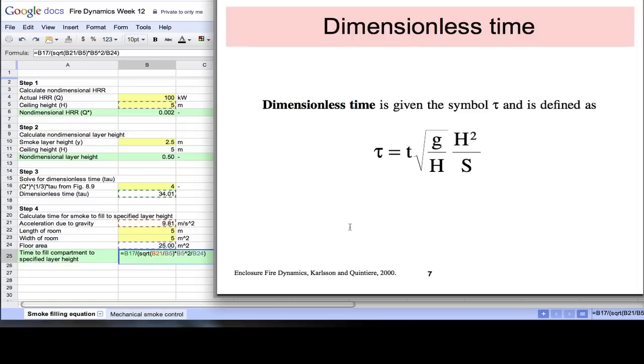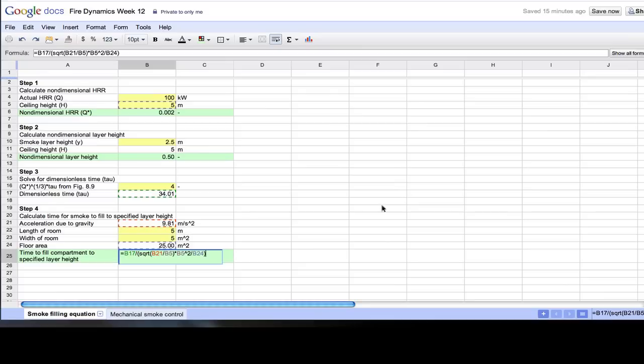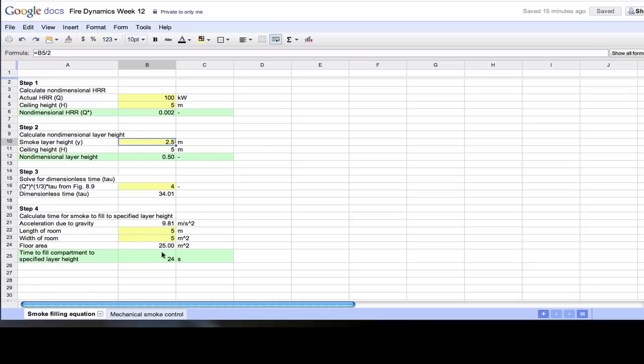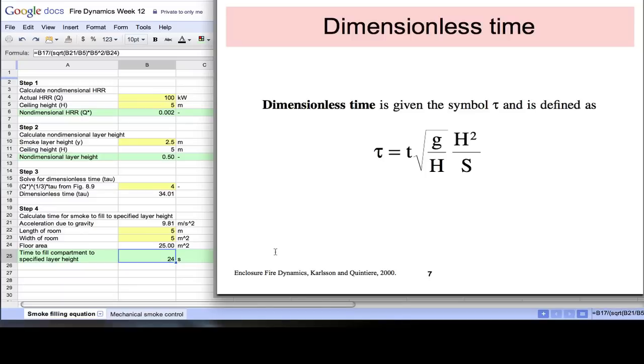Using the value of 4 from figure 8.9 divided by q* to the 1/3, I solve for dimensionless time tau. Then using the dimensionless time equation and inputting the room's length and width for the floor area, I solve for t — the actual time in seconds for the smoke layer to descend to 2.5 meters. I get out a time of 24 seconds for a 100 kilowatt fire in a room 5 meters high by 5 meters wide by 5 meters long.